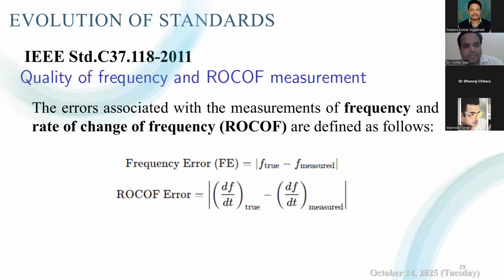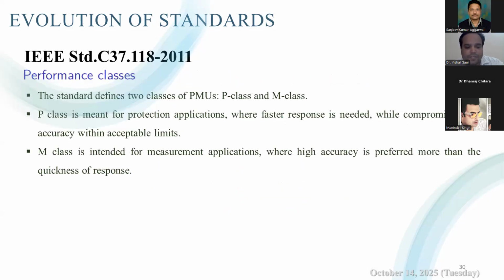Some of the other indices that the IEEE standard provides are for calculating the frequency error as well as the rate of change of frequency error. So this IEEE standard puts limits on all three error metrics, that is TVE (total vector error), frequency error, and rate of change of frequency error, to ensure that PMUs are reliable, not only in steady state but also during dynamic system events or dynamic conditions.